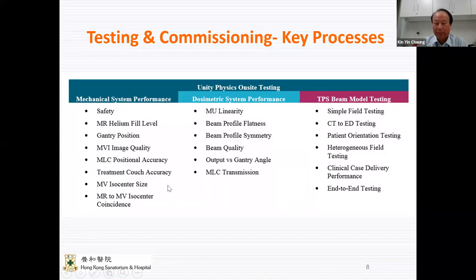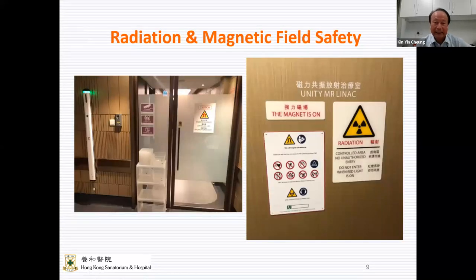And also, because of the MR system, the magnetic field will make a lot of things quite challenging to do. Particularly, you need dedicated MR compatible tools for beam data measurement, quality control, and so on. Also, the geometry of the system has a bore of limited size, so a lot of your equipment would not be applicable to this machine, and some procedures would be different because of this. Apart from that, the process or the concept behind it would be similar to a Linac. As I said, it has an MR system built into the machine.